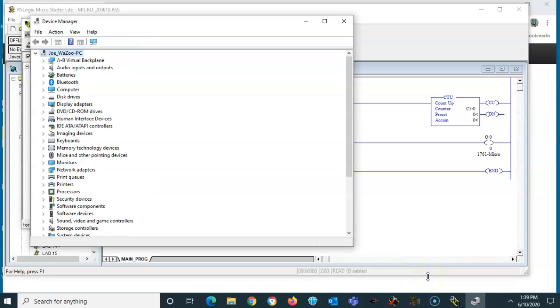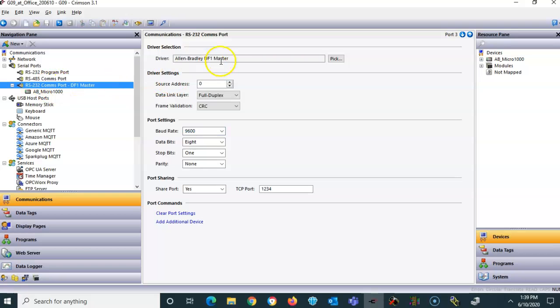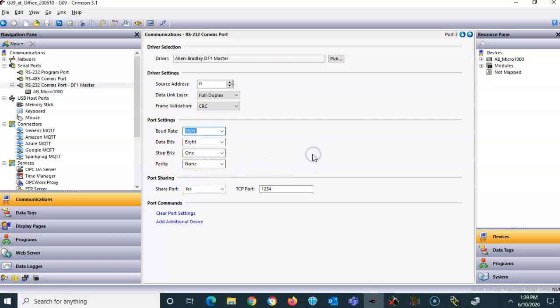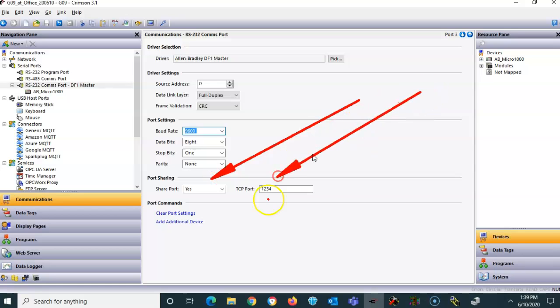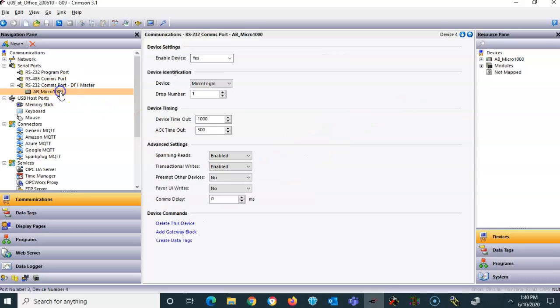I'm going to disconnect the cable from that and I'll plug in a cable from Red Lion, a CBL-GEN01 cable. Over at my Red Lion device, I've got a G09 here, one that's at the office, and I have an RS-232 port configured as an Allen Bradley DF1 master, 9600-8-1-none, the same as there. The only thing I've done different here is I've set up the port sharing down here and I've given it a port number of 1234.